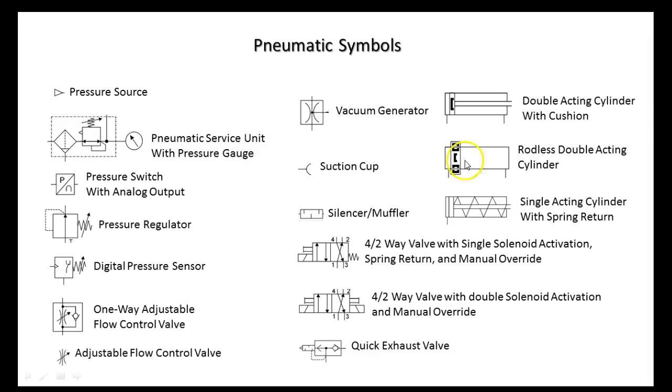Well, how do we cause motion? Either we put a band inside of the thing and it causes the band to move, and then whatever's going to move is attached to the band. Or we put a big old magnet inside that thing. So the piston is a big magnet. And then the cradle or whatever you're going to move rides on the outside and just attaches to the magnet. So when the magnet moves inside the rod, the actuator moves.